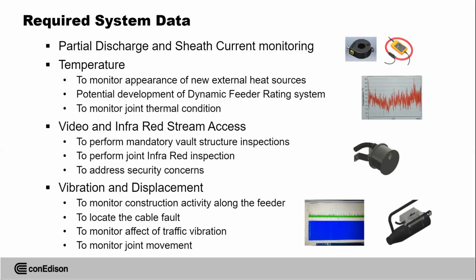So partial discharge, we see as an important part of the system. How important is that? When you energize the system, we believe it's important to do a partial discharge reference scan, just to have the baseline for your future analysis. It's the same thing as a young person coming to a doctor and doing an EKG. And then every 5-10 years, repeating that EKG, and the doctor can compare and see if any changes are going on. It doesn't mean you need to rush onto a surgery table right away. Of course not. But it will give an early indication if something is going on with your system. Same thing with partial discharge here.